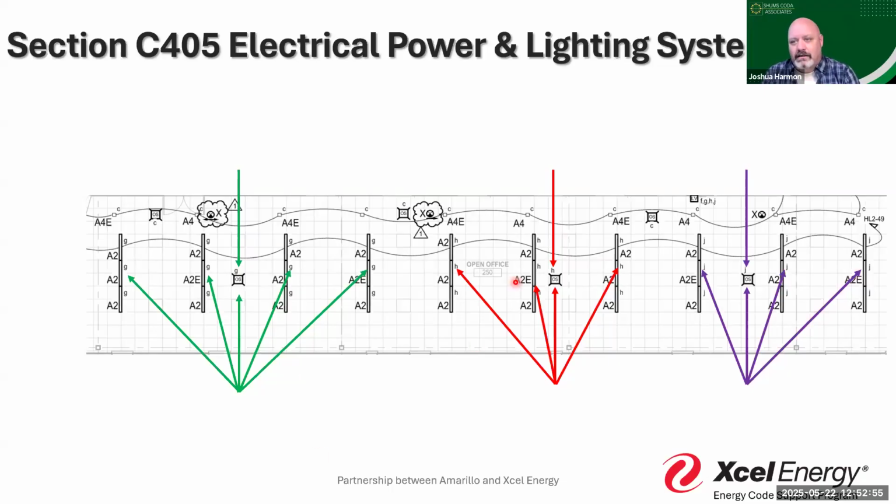I'm not going to double check that. At least at plan review, I'm not checking whether H connects to all of these through a wire. That's going to be an inspector's job. I'm going to say all of these systems, all these lighting fixtures go off of H. So when you have that functional testing, you say, hey, turn on the lights, and they all turn on based on where I'm standing, right?